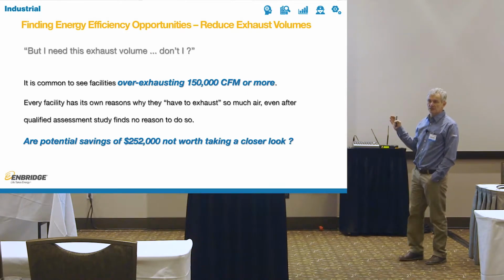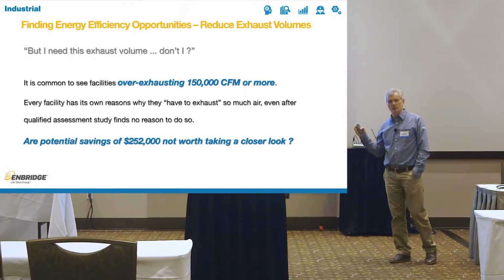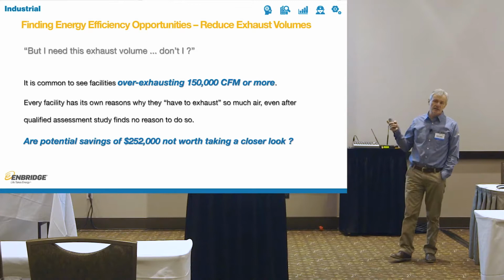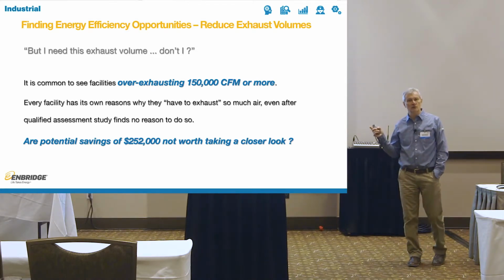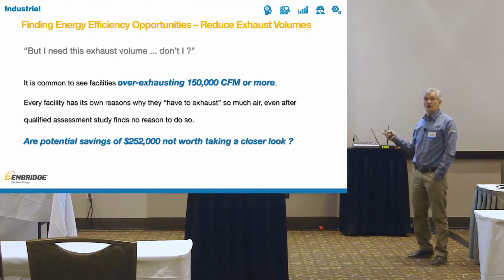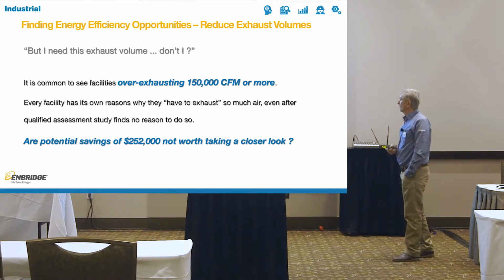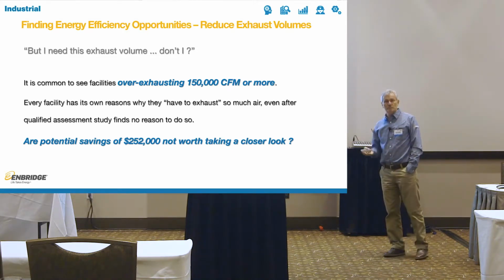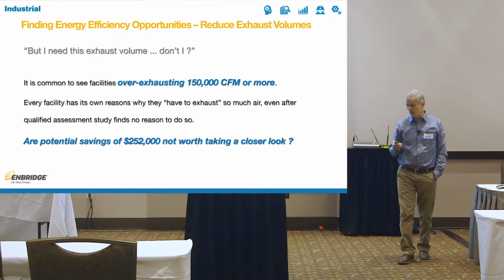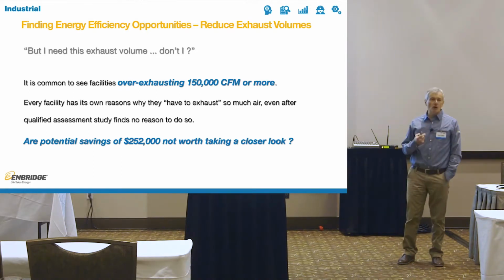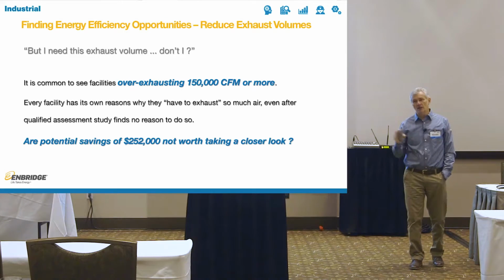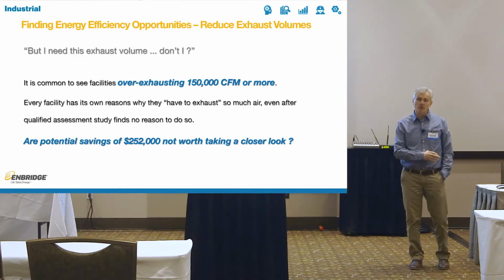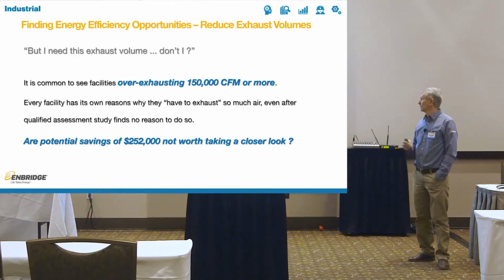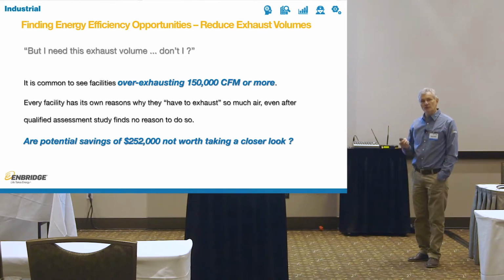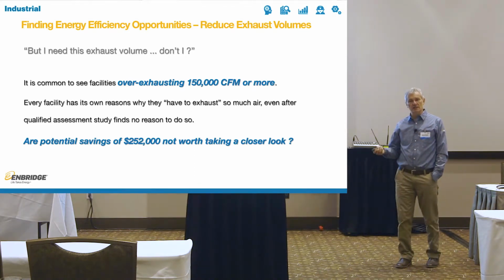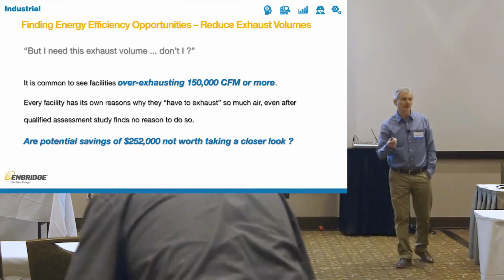Now I'm beginning to be surprised when I see, in the last air balance report that we've done, 385,000 CFM of additional exhaust in a facility that's about 150,000 square feet. So 150,000 CFM, that's pretty much average in Southern Ontario that you see. And they all have their reasons why they have to exhaust. My God, people would die, people would freeze, people would do all sorts of stuff. We just have to do it. But nobody is willing to actually pony up and do the assessment of it. For some reason, people are very leery of doing assessment.